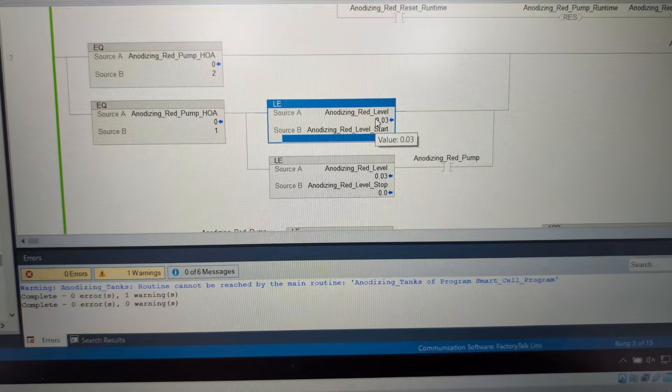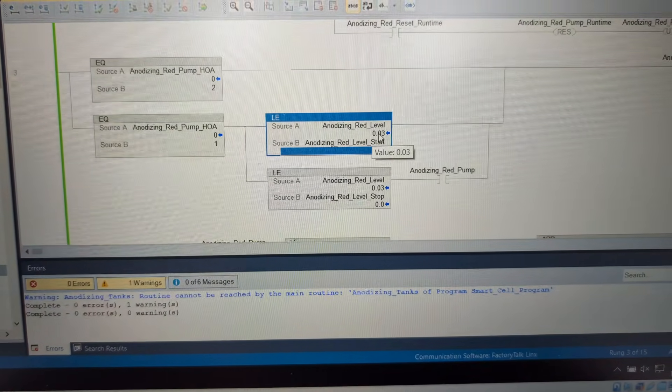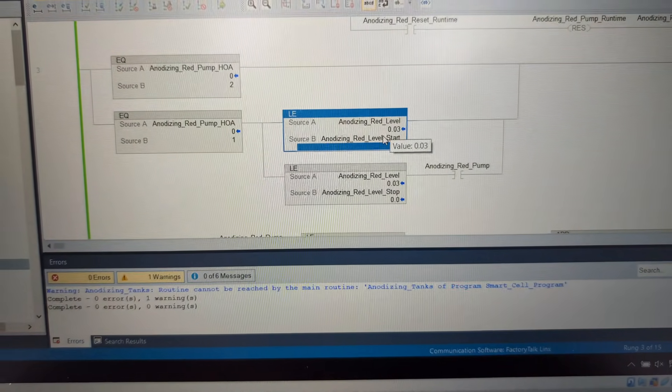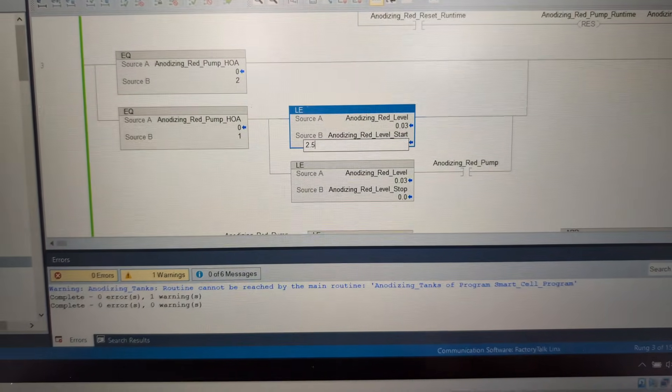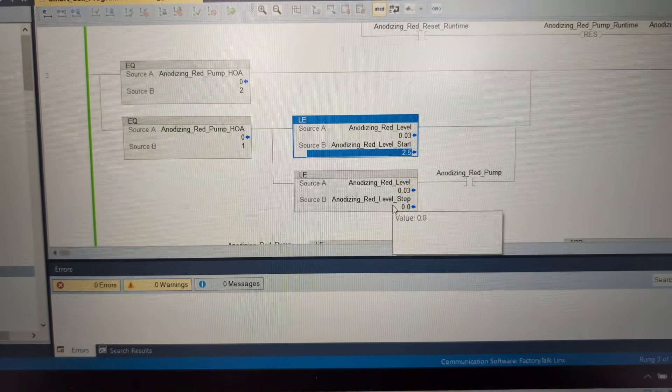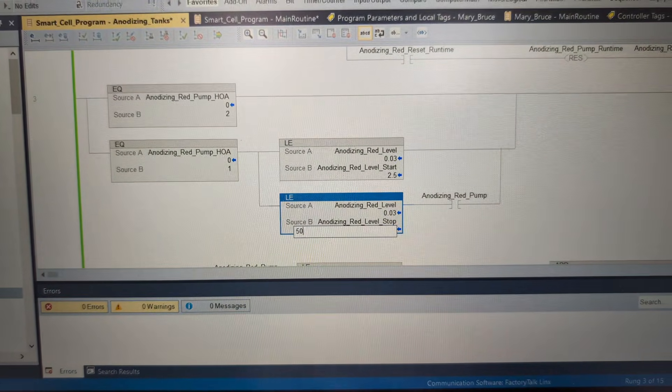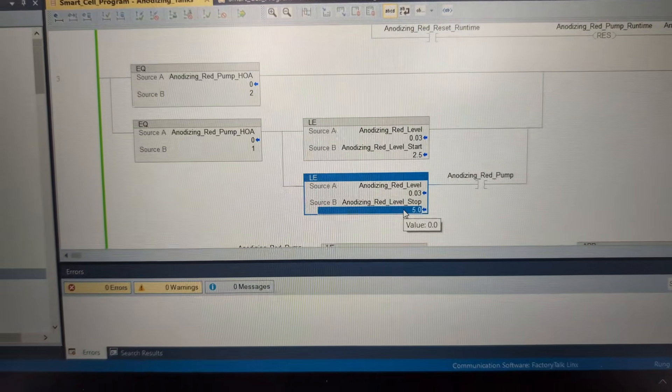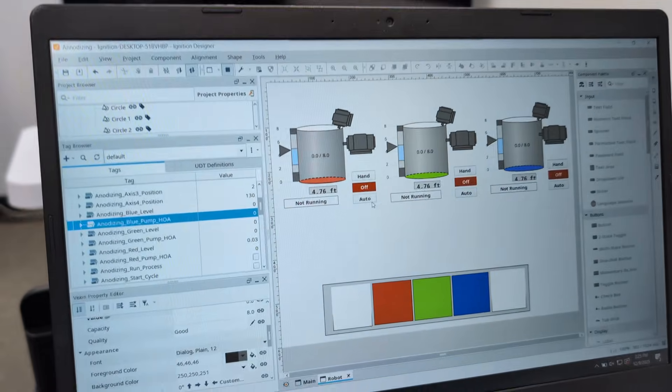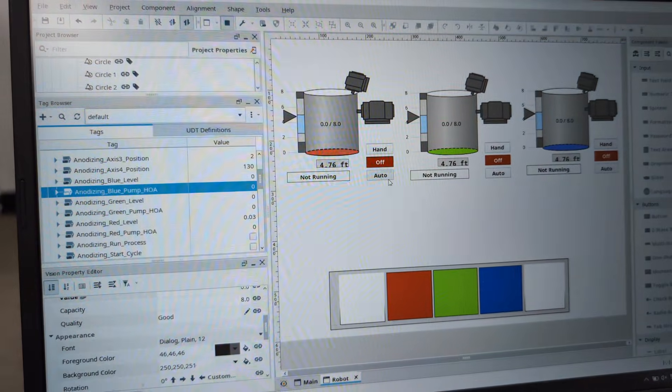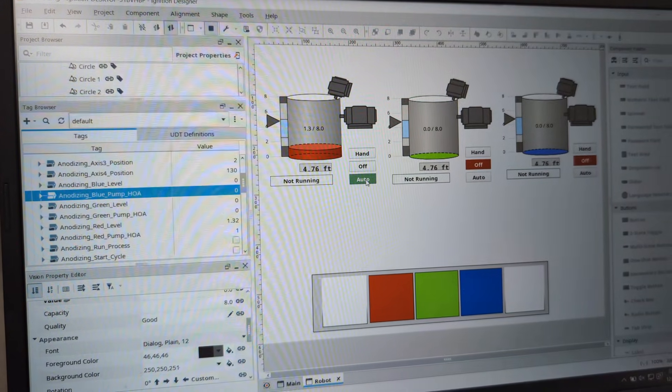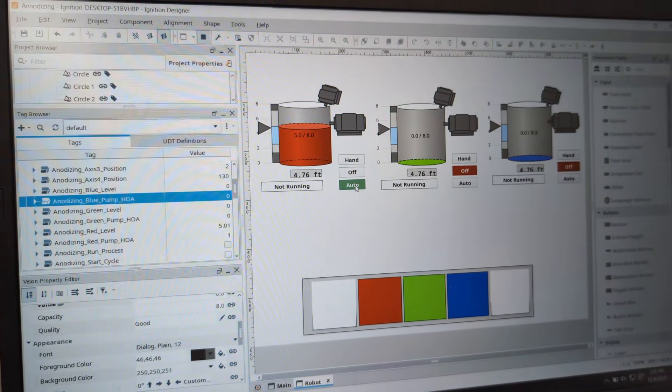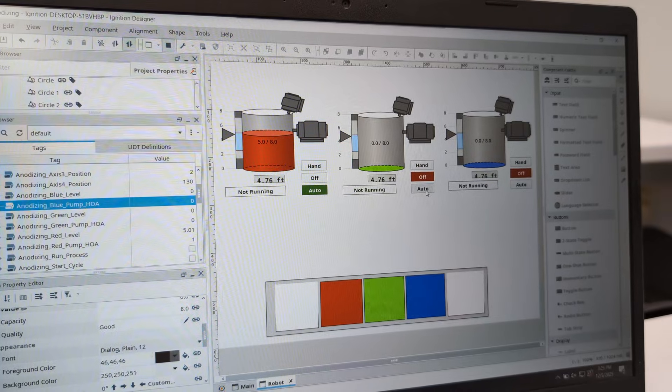It's supposed to start pumping if it's less than two and a half. Right now zero, or actually point zero three, so it did actually pump - it pumped a little fluid. That should have been 2.5 and our stop level is five. Whoops, that's 50 - now we'll flood our room. And now if we switch that over into auto, our tank starts filling up. Go ahead and switch the other two into auto. And both of those are full, which means our tanks are ready to do some dipping.